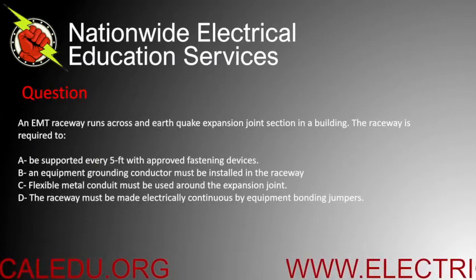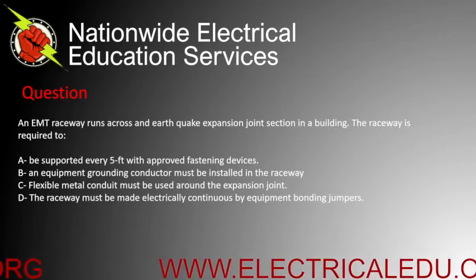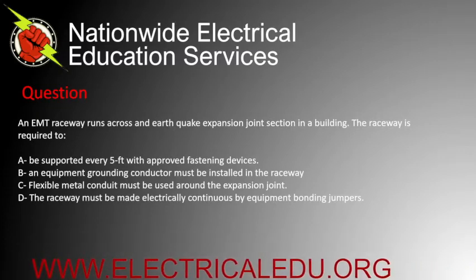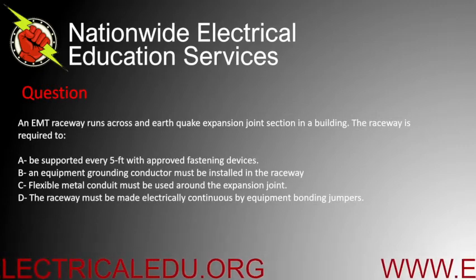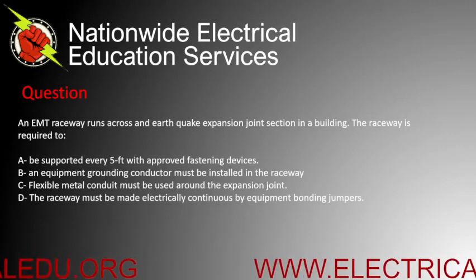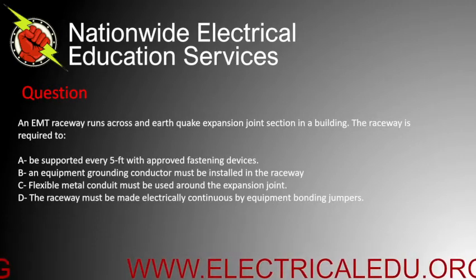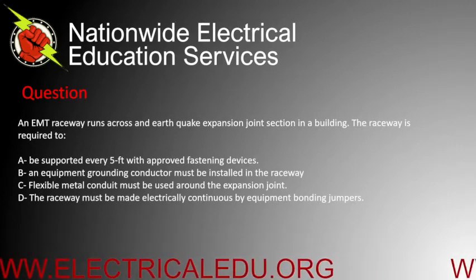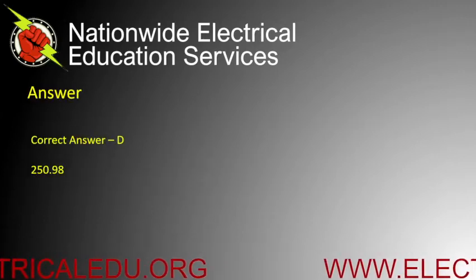An EMT raceway runs across an earthquake expansion joint section in a building. The raceway is required to: A) be supported every five feet with approved fastening devices, B) have an equipment grounding conductor installed in the raceway, C) use flexible metal conduit around the expansion joint, or D) the raceway must be made electrically continuous by equipment bonding jumpers. D is the correct answer.